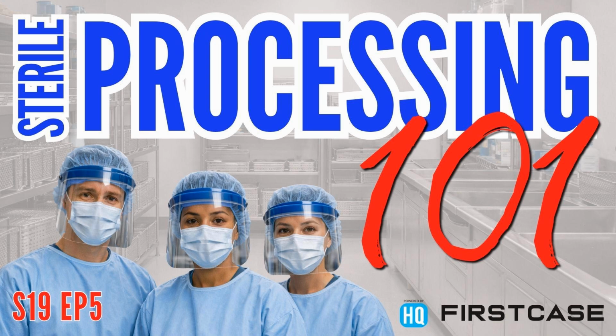The other big change that they made with IUSS is that it needs to be done in a rigid container system that's been validated by the FDA for immediate use steam sterilization. So again, gone are the days where we had that little open flash pan where the instruments are just open to the air, because again, the big risk with IUSS is that transfer to the back table. So we don't want somebody holding this hot pan with tongs open to the air, trying to elbow around people through the sub-sterile and taking it into the back door of the OR. We want it to be in a rigid container system so that at least we can get it right next to the back table and then open it up and have that instrument there. So those are the two big changes: full reprocessing and an approved rigid container system.